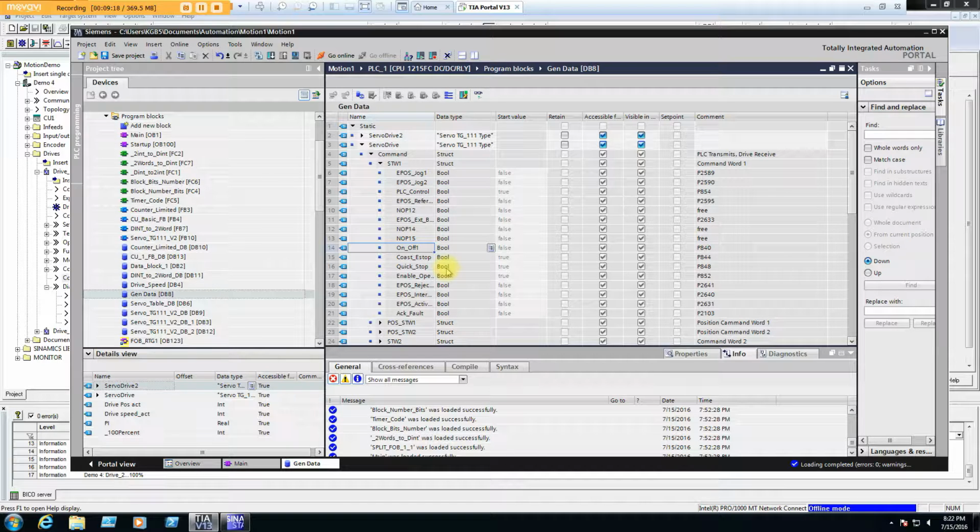Real commonly, I've sent stuff back and forth with Rockwell. They use the Intel standard, so they're low byte first, little Endian. So you always got to remember to swap those bytes around. I've done Honeywell DCS communications. They're also little Endian. Actually, in the Honeywell, they can swap the bytes because they're used to dealing with all kinds of different vendor equipment. So they have that feature built in that they can do right at the communication level to swap them. Some of the communication gateways are the same way. You just flip a little bit in the config, tell it to swap bytes, and then it swaps the bytes for you.